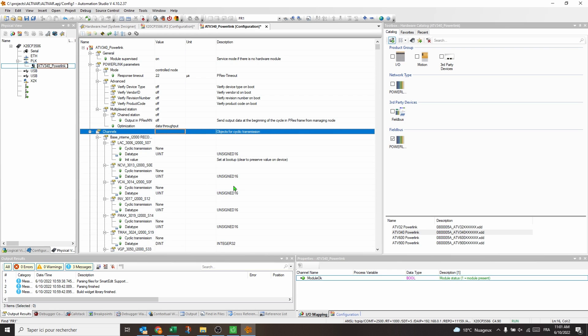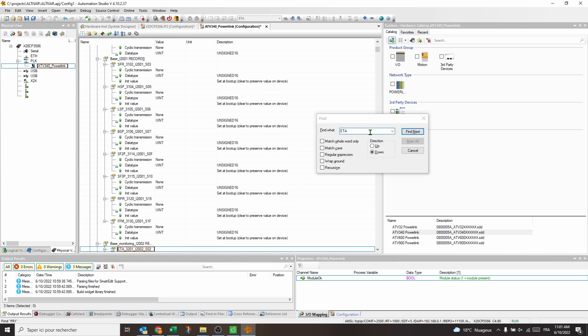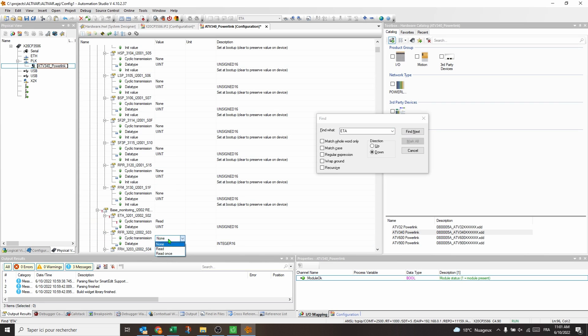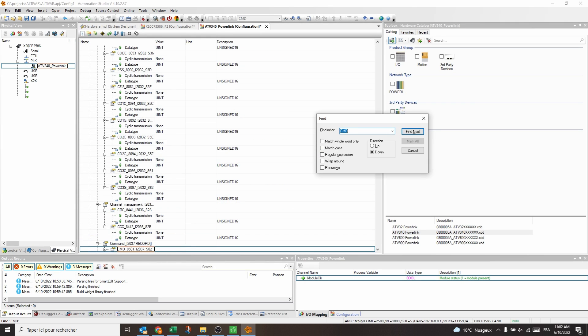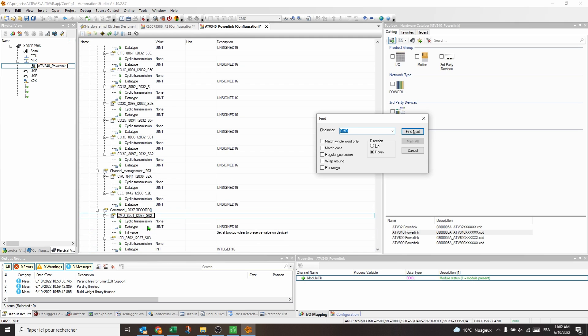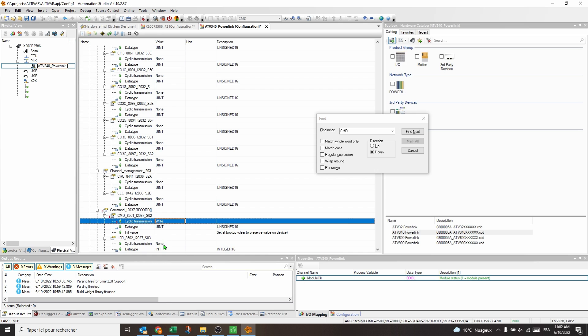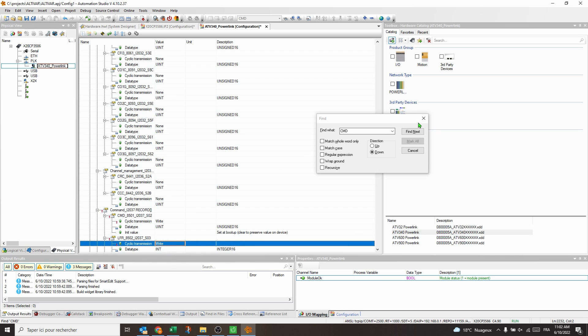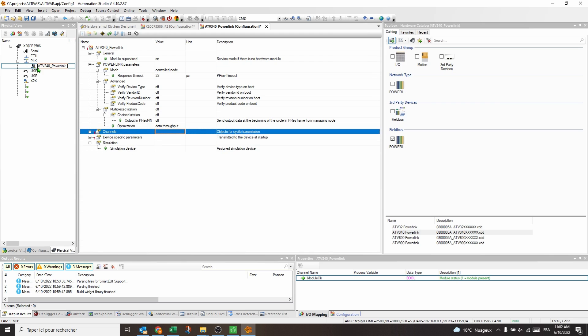Expand the channels to configure the parameters that will be exchanged cyclically. In read mode, select ETA for drive status and RFR for motor speed in 0.1 Hz. In write mode, select CMD for command and LFR for reference in 0.1 Hz. Build the project.